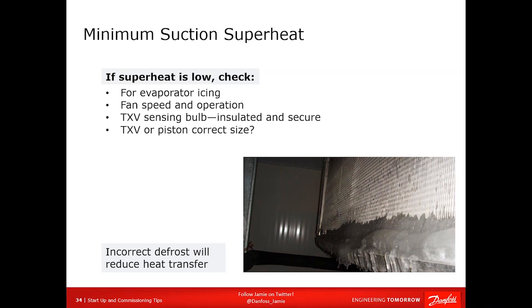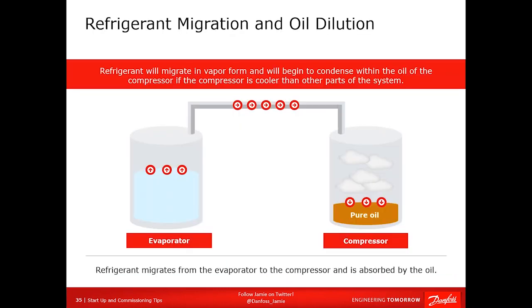If the TXV is oversized, that's not going to be an issue unless it's grossly oversized, the superheat's been reduced too much on it, and/or the sensing bulb is picking up heat that it shouldn't be. If the piston is oversized, it's going to immediately flood the compressor as soon as it gets warm outside. All right.